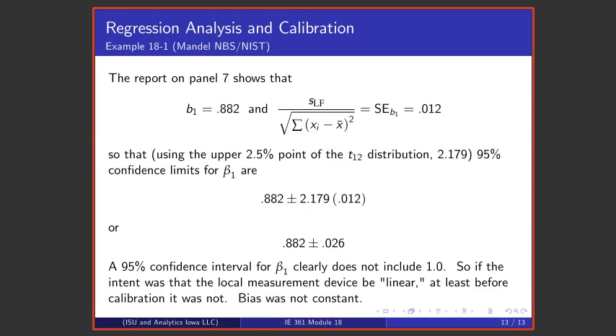If one looks at the report on panel 7, the slope of the least squares line is 0.882 and the standard error for the slope of the least squares line is 0.012 so that confidence limits for the slope of the relationship between x and average y are these. Those limits, those are 95% confidence limits, those limits do not include one. And so one knows pretty definitively that this is not, that Mandel's data did not come from a device that one would call linear in the sense of having constant bias.